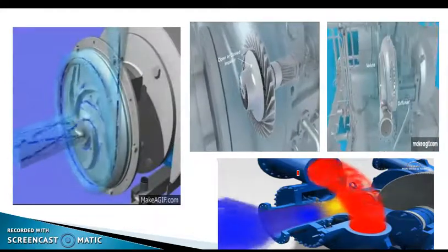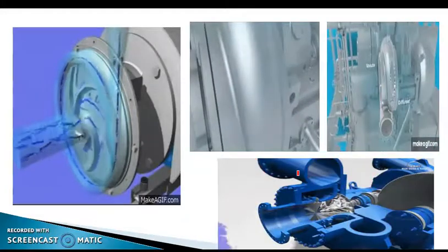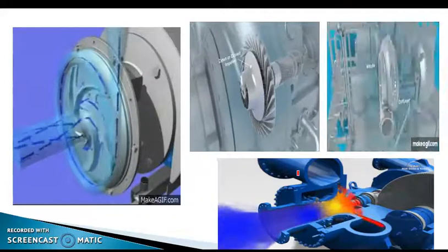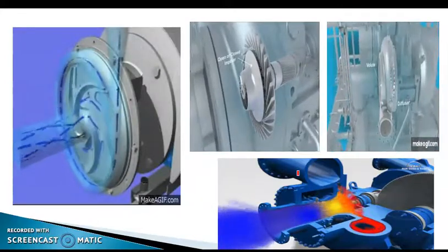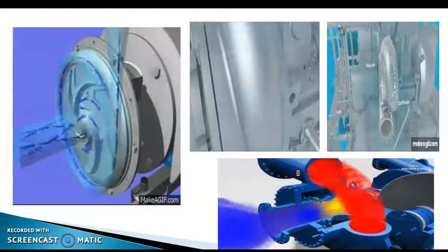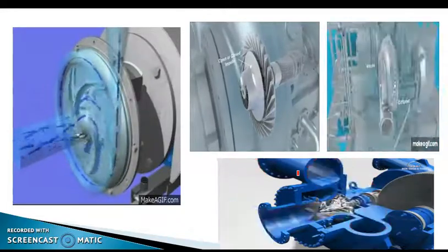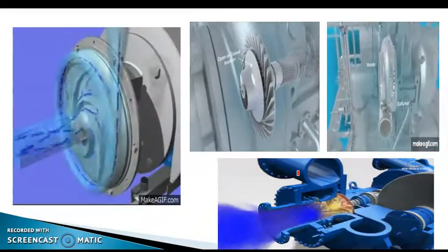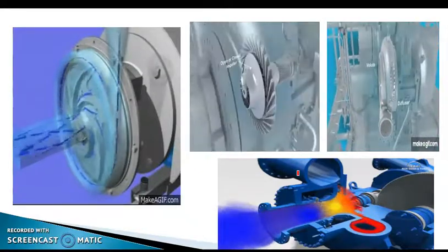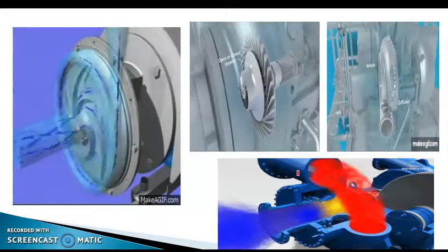The high speed impeller leaves the vapor refrigerant at high velocity at the vane tips of the impeller. The kinetic energy thus attained at the impeller outlet is converted to the pressure energy when the high velocity vapor refrigerant passes over the diffuser.